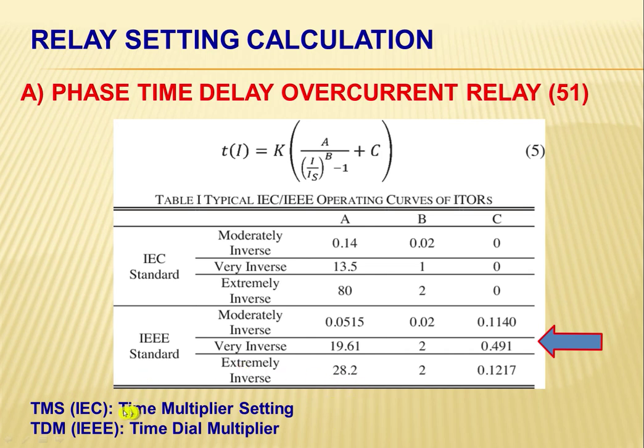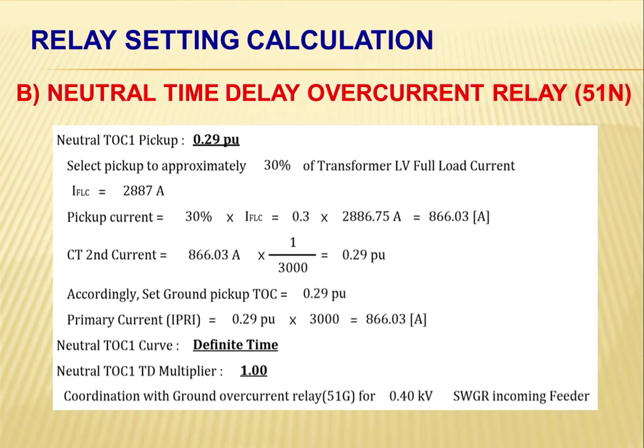Okay. For IEC, it is called TMS, time multiplier setting. For IEEE, it's called TDM, for the time dial multiplier. Okay? Next, we're going to calculate the neutral time delay overcurrent relay setting, or the 51N.